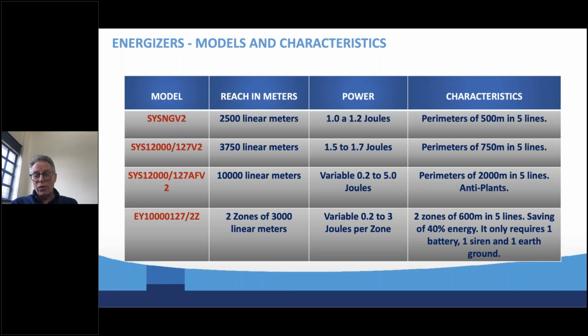We also have another model with 2 zones. Normally we use one equipment per zone, and the recommended zone length is from 300 to 350 meters. Each of these units gives you only 1 zone, so you know where the cut happened. But with this 2-zone equipment, you can manage 2 independent zones with the same unit, and it gives you about 3 years of service.